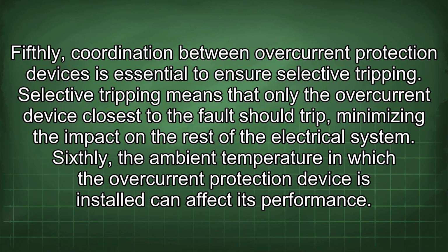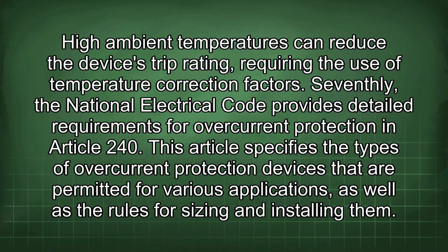Fifthly, coordination between overcurrent protection devices is essential to ensure selective tripping. Selective tripping means that only the overcurrent device closest to the fault should trip, minimizing the impact on the rest of the electrical system. Sixthly, the ambient temperature in which the overcurrent protection device is installed can affect its performance. High ambient temperatures can reduce the device's trip rating, requiring the use of temperature correction factors.